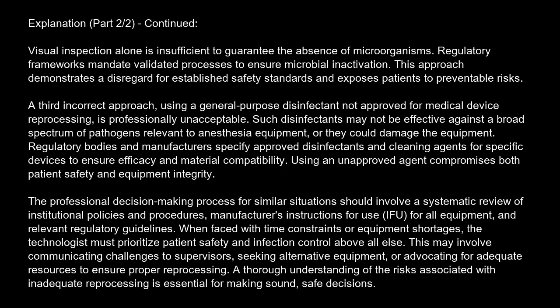Such disinfectants may not be effective against a broad spectrum of pathogens relevant to anesthesia equipment, or they could damage the equipment. Regulatory bodies and manufacturers specify approved disinfectants and cleaning agents for specific devices to ensure efficacy and material compatibility. Using an unapproved agent compromises both patient safety and equipment integrity.